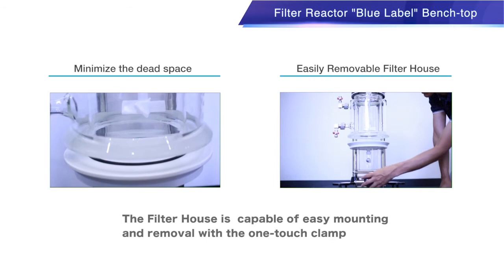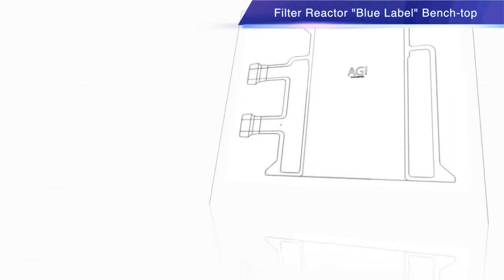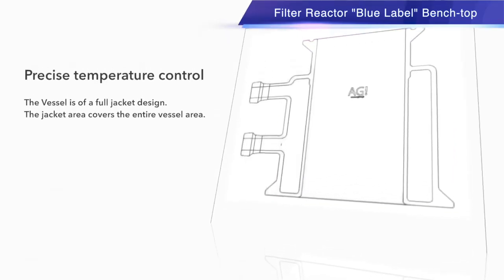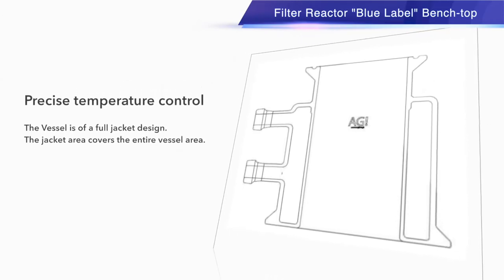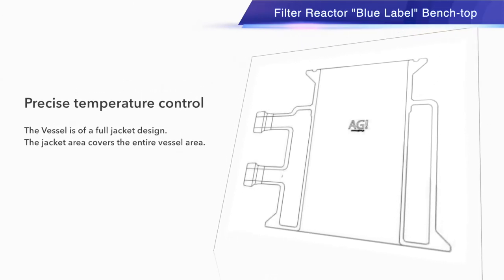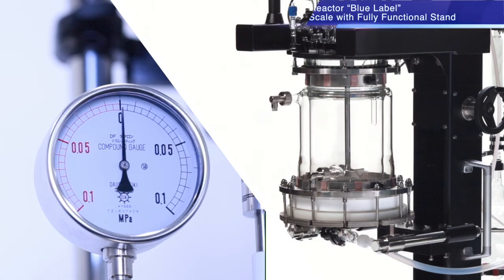The filter house is designed to minimize the dead space and is capable of easy mounting and removal with the one-touch clamp. The vessel is of a full jacket design. The jacket area covers the entire vessel area.